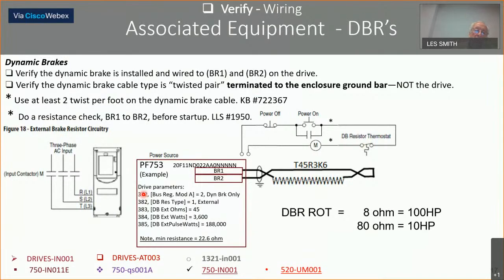And here on the drives, if we're doing dynamic braking resistors, there's going to be parameters relative to the drive dynamic brake setting. Here, first of all, we're going to turn the bus regulator off, and we're going to turn on dynamic brake. It says "only" because there's some other settings on the architectural drive, which means dynamic brake first and then frequency adjust, or frequency adjust and then dynamic brake. And what that means is there's another manual out there called a 750-RM reference manual. And it'll tell you that that chopper will turn on 8 volts before the normal threshold if it's just a dynamic brake only. So you have 2 levels that the dynamic brake will come on. It'll let the drive try to correct things.